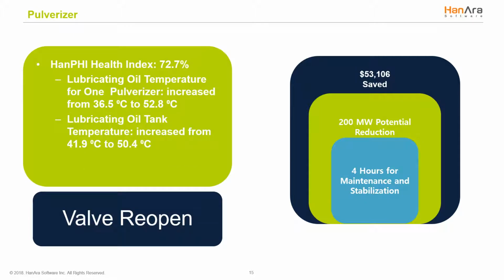The fourth case occurred in February 2016 when HanPHI helped a 560 megawatt thermal power plant save over $50,000 by preventing a pulverizer trip. On February 3rd, HanPHI identified a temperature increase of the lubricating oil for the plant's 2 pulverizers. The temperature of the lubricating oil for one pulverizer increased from 36.5 degrees Celsius to 52.8 degrees Celsius, and the lubricating oil tank temperature increased from 41.9 degrees Celsius to 50.4 degrees Celsius. The temperature of the lubricating oil and tank for the other pulverizer increased as well, dropping the signal's health index to 72.7%.